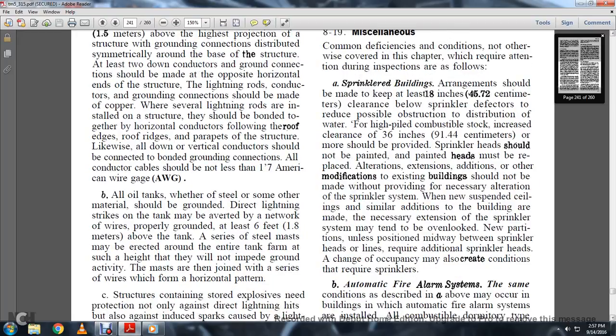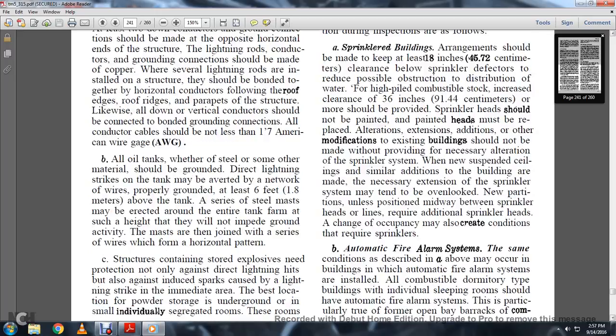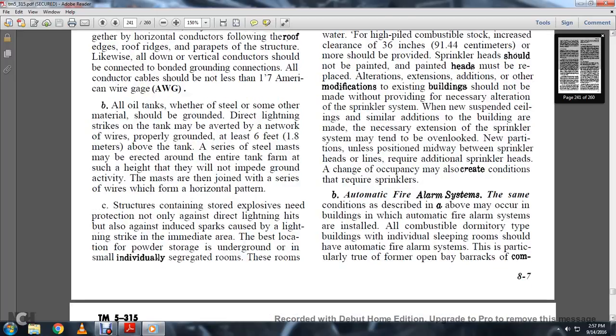All oil tanks, whether steel or some other material, should be grounded. Direct lightning strikes on the tanks may be averted by a network of wires properly grounded at least 6 feet above the tank, and a series of steel masts may be erected around the entire tank farm at such a height that will not impede the activity on the ground. These masts are joined with a series of wires in horizontal patterns.